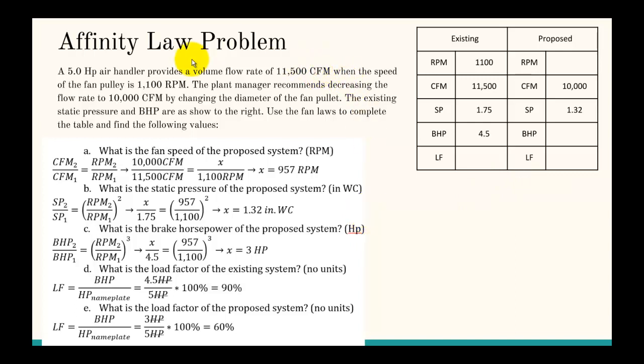You wouldn't get this full problem on the CEM exam, but you could get pieces of it. A 5 horsepower air handler provides a volume flow rate of 11,500 CFM when the speed of the fan pulley is 1,100 RPM. The plant manager recommends decreasing the flow rate to 10,000 CFM by changing the diameter of the fan pulley. The existing static pressure and BHP are as shown. Use the fan laws to complete the table and find the following values. I'm not going to complete the table, but I'm just going to find the values here.